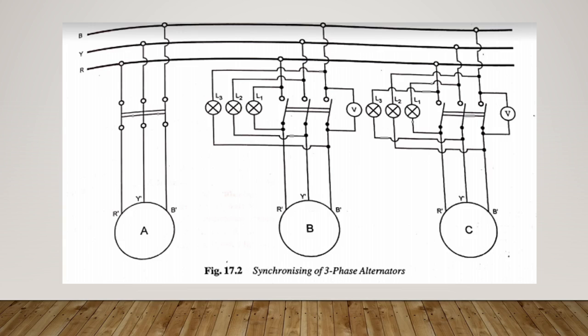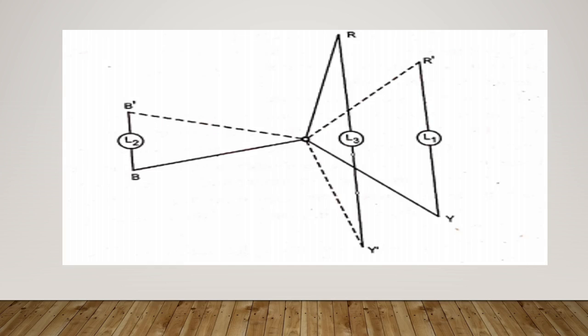So let the voltage star R Y B be referred to the bus bars, and the star shown in dotted lines, that is R dash Y dash B dash, to the incoming machine. The instantaneous voltages across the three lamps will be given by the phasors R Y dash, R dash Y and B B dash, as we can see in this figure. When the frequency of the incoming alternator is the same as that of the bus bars, both phasor diagrams will rotate in space with the same angular velocity, so the potential difference across each lamp will remain constant.